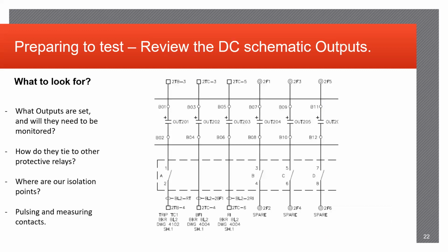Reviewing the DC schematics, identifying the outputs specifically. What outputs are going to be monitored? What ties to the other relays? Verifying your isolation points and pulsing and measuring contacts. So during testing, you'll want to identify the correct operation of each output and verify that it picks up properly. So for example, here on this out 201, it's going to be tripping TC1 on your breaker BL2.